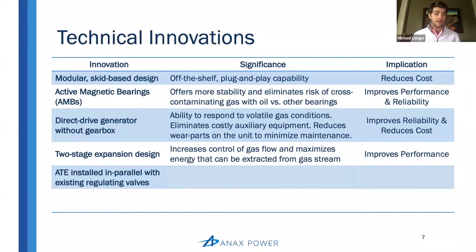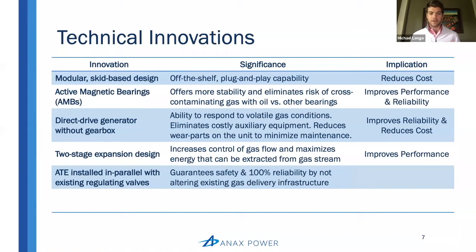The next innovation is that the Anax Turbo Expander (ATE) is installed in parallel with existing pressure regulating valves. This is arguably the most important innovation because it allows us to guarantee safety and 100% reliability by not altering the existing gas delivery infrastructure — critical, crucial infrastructure that is oftentimes the lifeline of the companies and plants we serve. Through our customer discovery process, we knew we didn't have a chance of being successful unless we could guarantee this safety and 100% reliability. By going in parallel with the existing pressure regulating valves, we actually add an additional layer of safety redundancy, making the system a little bit more safe.